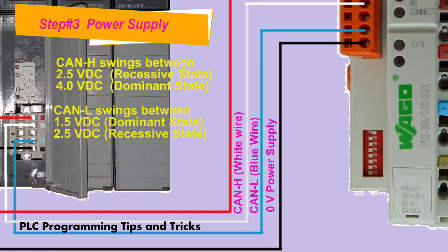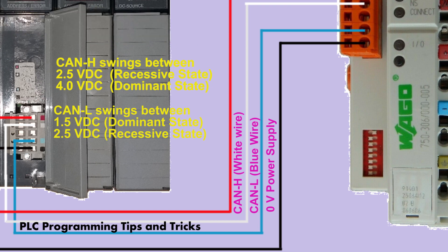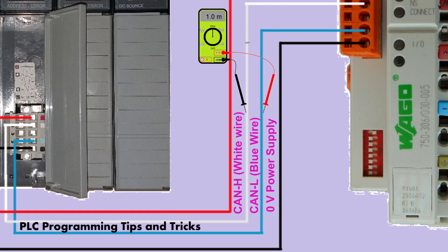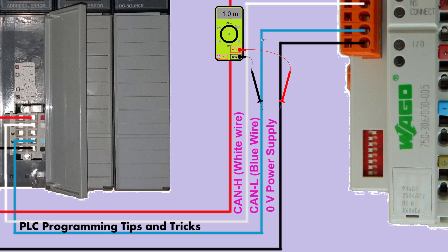Verify network voltage: DeviceNet is a three-wire differential voltage network. Communication is accomplished by switching the CAN high white wire and CAN low blue wire signals relative to the V-negative black wire. The CAN high swings between 2.5 volt DC in the recessive state and 4.0 volt DC in the dominant state, while the CAN low swings between 1.5 volt DC in the dominant state and 2.5 volt DC in the recessive state. Check for shorts of CAN-H or CAN-L to the shield, or short circuit with the power supply zero voltage.